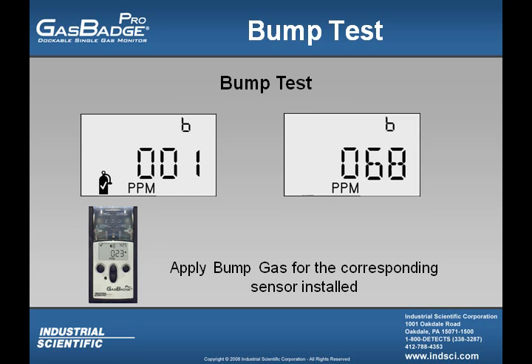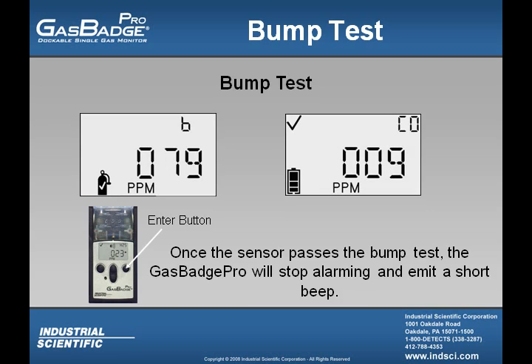Once the user has pressed the enter button, they must apply the calibration gas. They will see the display on the instrument start to rise, much like the display on the right. Once the GasBadge Pro is done performing the bump test on the sensor, and the sensor passes the bump test, the instrument will emit a short beep and go back to the real-time operation screen, just like the screen we have on the right.